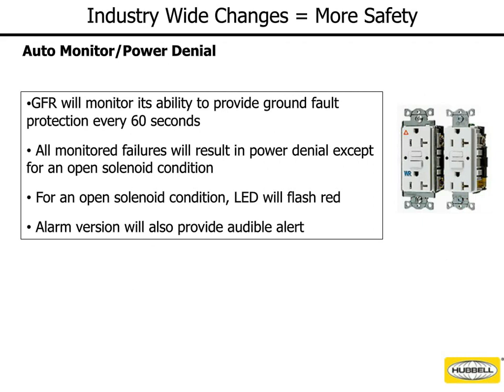So the ground fault will monitor its ability to provide ground fault protection. You still have the ability as a user to push the test button. We still recommend that you have a preventive maintenance program and that you're manually testing your ground faults every 30 days. But the new product, every 60 seconds, will check the circuit, make sure it's operating properly, and it'll deny power. Now, the 60 seconds is Hubbell's standard. The UL requirement is that it tests itself at a minimum every 15 minutes. So every manufacturer can arbitrarily choose whether it's 5 minutes or a minute. Any way you look at it, it's going to be safer than the world we have today where people aren't pushing the test and reset buttons at all.